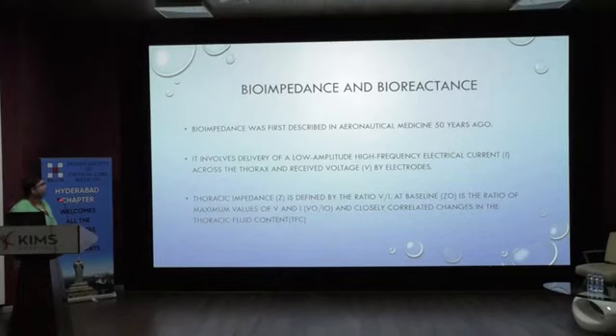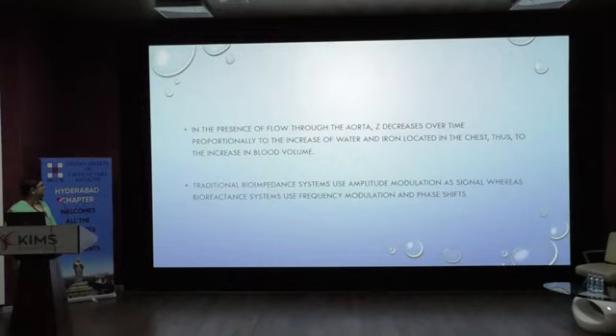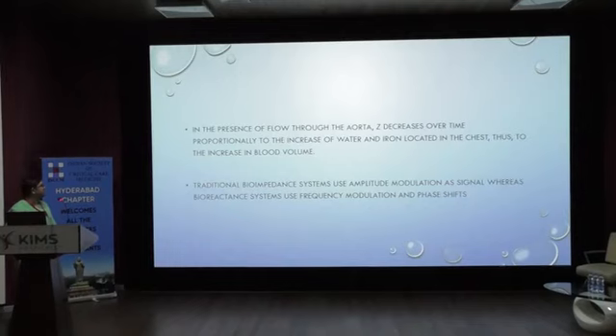Bioimpedance was first described in aeronautical medicine almost 50 years ago. It involves delivery of a low amplitude, high frequency electric current across the thorax and measurement of received voltage by electrodes. Impedance is defined as the ratio of voltage to current. The baseline ratio is related to changes in thoracic content — in the presence of flow through the aorta, this impedance value changes over time proportional to increases in water and blood volume in the chest.